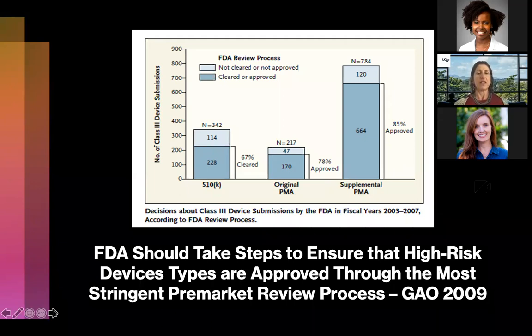In fact, most of them, as you can see, were going through a supplemental process, which sometimes could be appropriate, but sometimes may not be appropriate, because it's very hard to know when you're not doing clinical testing whether a small change you may have made in the equipment, the manufacturer, the lead material is actually going to improve the device or not improve the device, but the supplement allows you to make that change without any clinical testing beforehand. As you can see, most of the high-risk devices on the market get on the market through the supplemental PMA pathway.